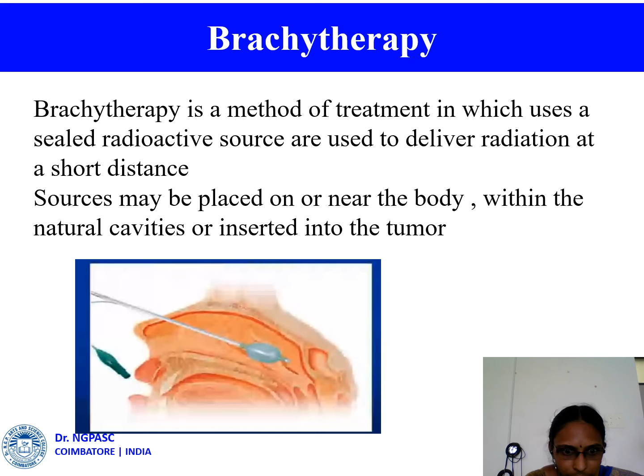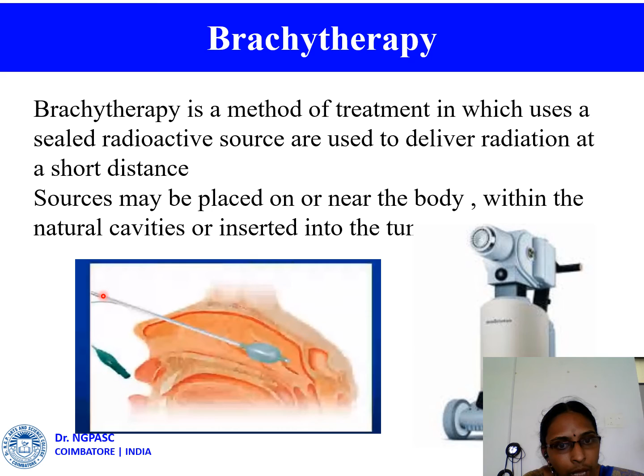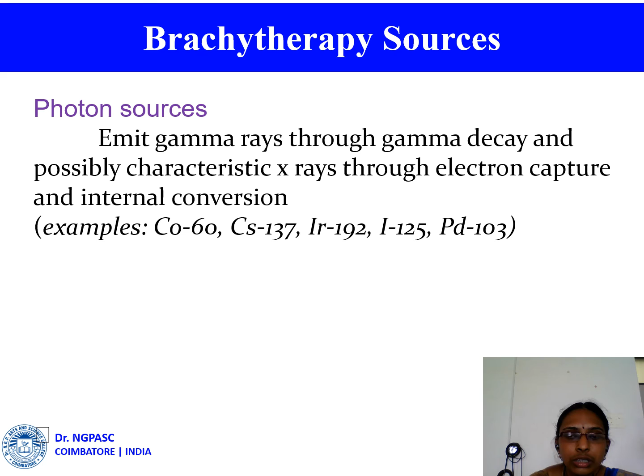In this place we are going to place the radioactive source. It is the applicator which is connected to the brachy machine via a transfer cable. This is the brachy machine. Here it has a hole, so the applicator is connected through the transfer cable to the treatment head of the brachy machine. In the treatment head, we have the radioactive sources. During the treatment, the radioactive source comes to the end of the treatment head and is transferred via the transfer cable to the applicator to treat the tumor. After the irradiation, the source is sent back to the treatment head with the help of motors present in the brachy machine.